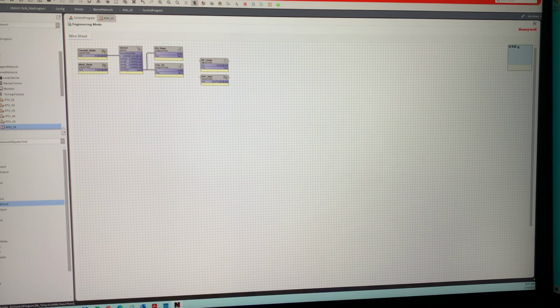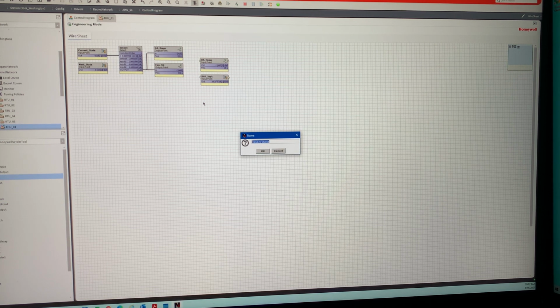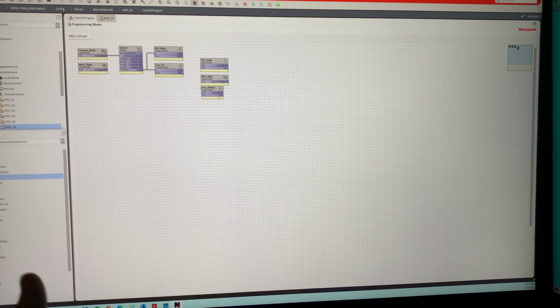So we have our discharge air temp, our DAT set point. Then we're going to need a binary input. We're going to call this fan status. So basically what we want to do is we want to make sure that our PID is being enabled when there's a fan status.